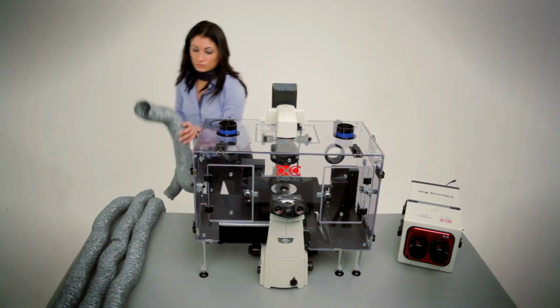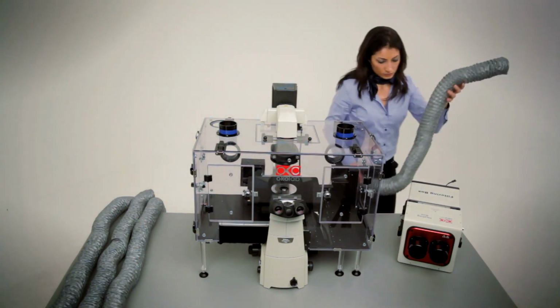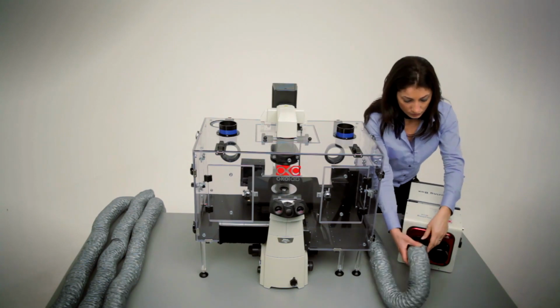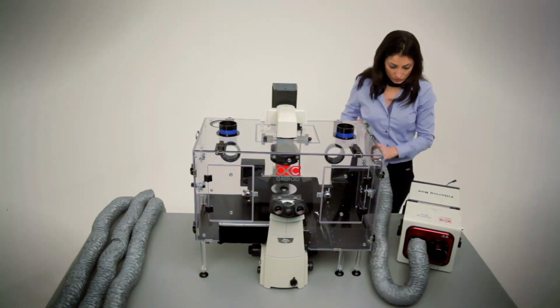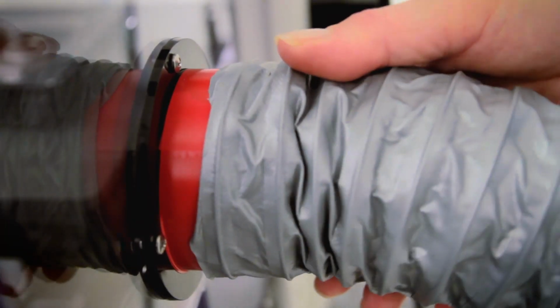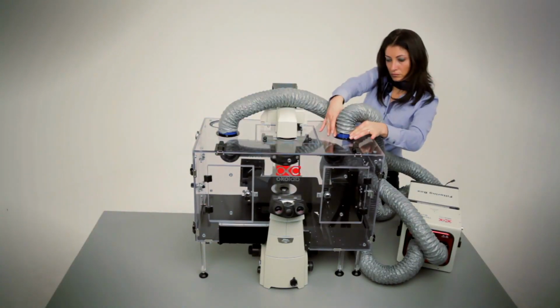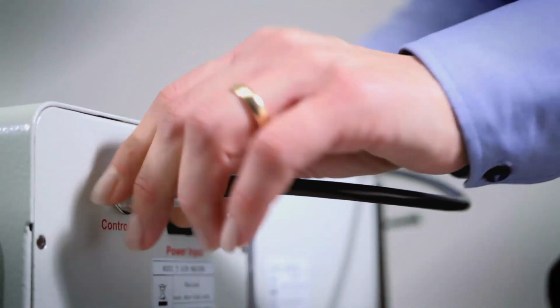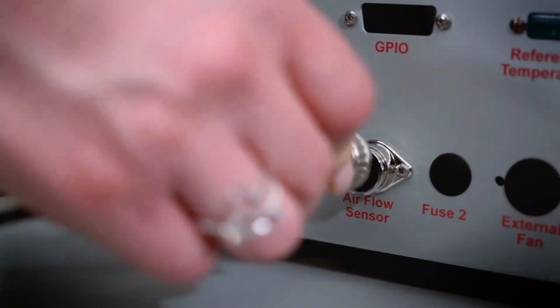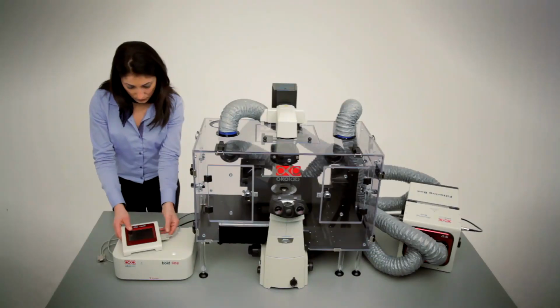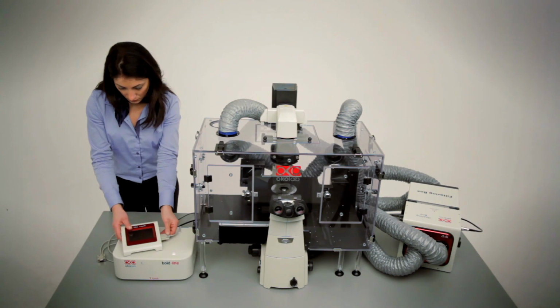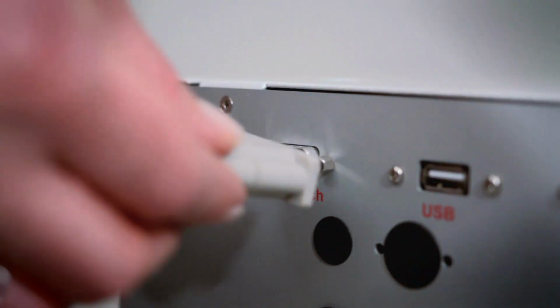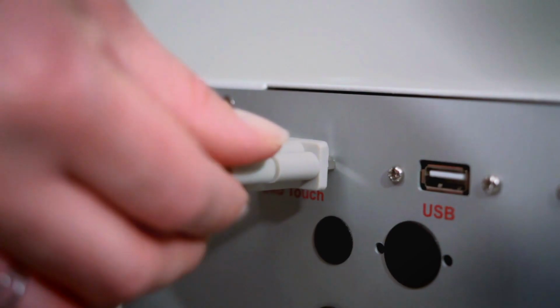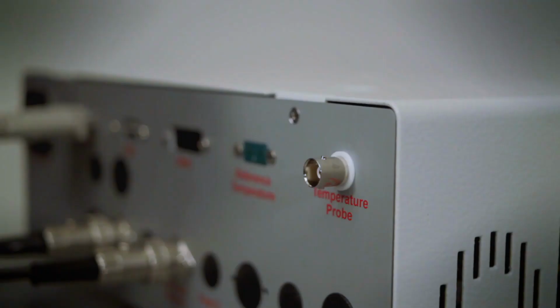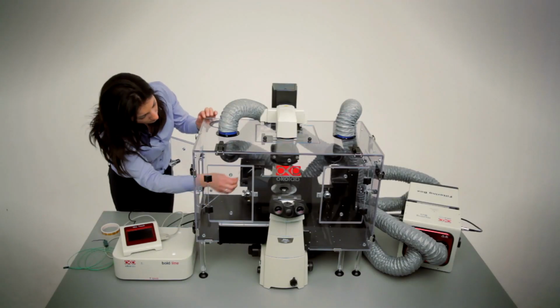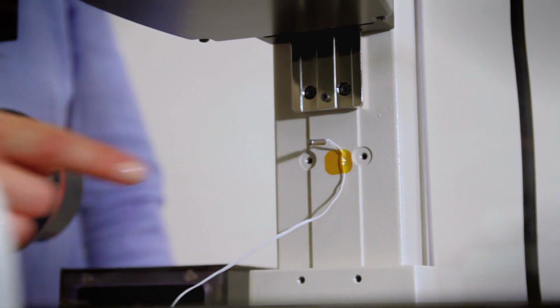Position the air heater within 1 meter from the microscope and use the gray flexible tubes to connect it to the enclosure. Mind the red and blue color coding. Connect the air heater and the flow rate sensor to the temperature controller. Connect the touchpad to the only RS-232 port of the controller. Connect the room temperature sensor to the controller and attach it to the microscope pillar.